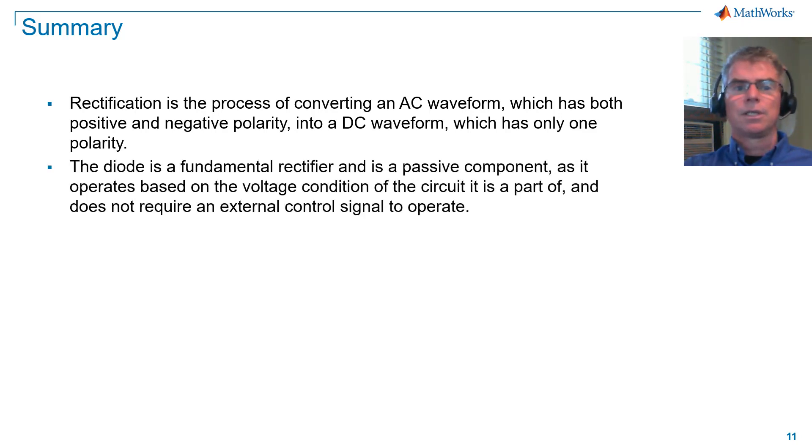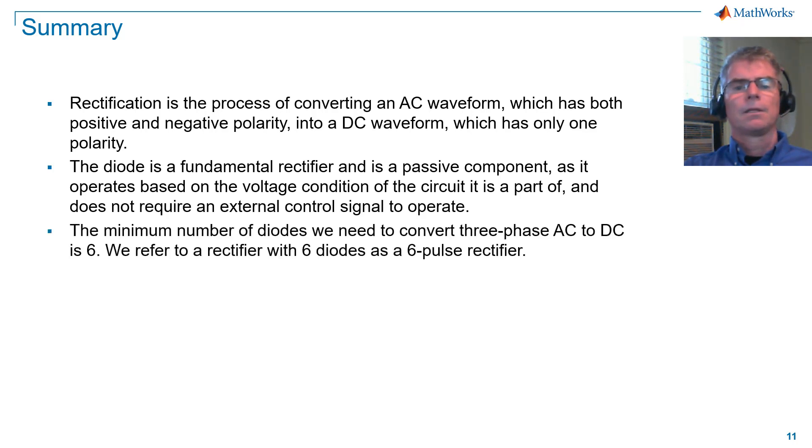The diode is a fundamental rectifier and is a passive component, as it operates based on the voltage condition of the circuit it's a part of, and does not require an external control signal to operate. The minimum number of diodes we need to convert three-phase AC to DC is 6. We refer to a rectifier with 6 diodes as a 6-pulse rectifier.